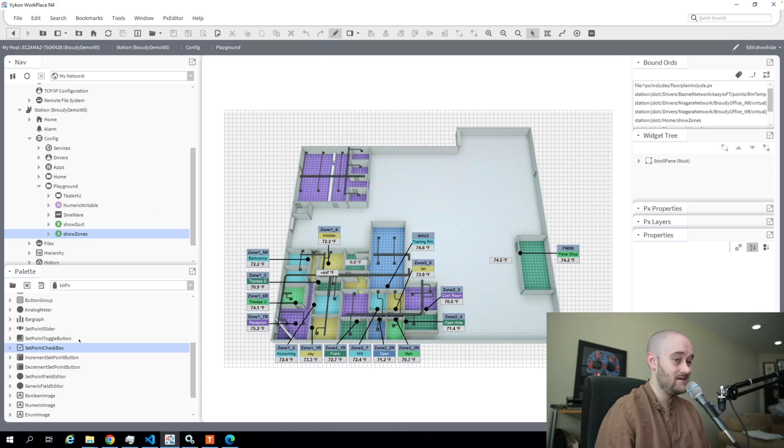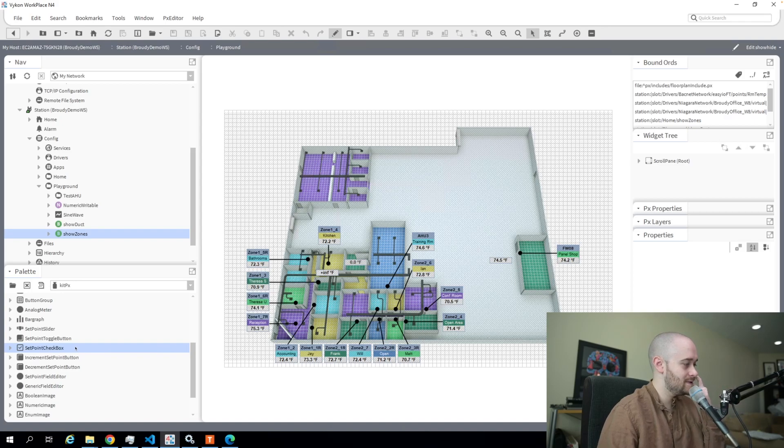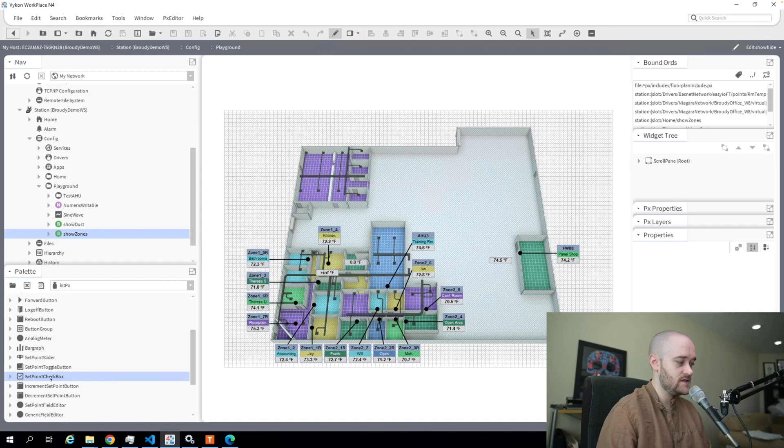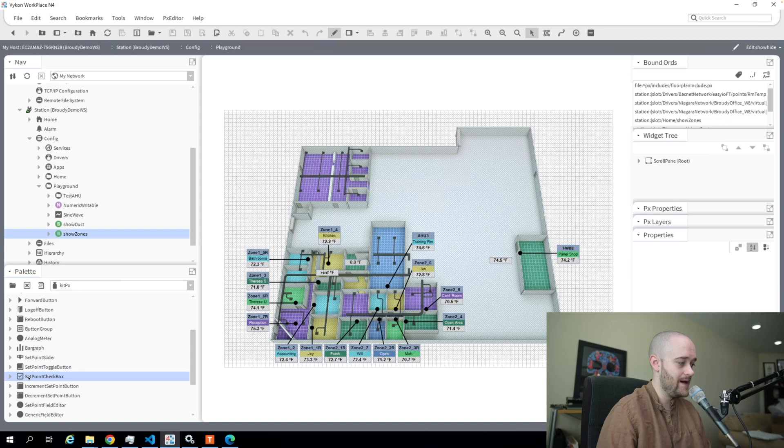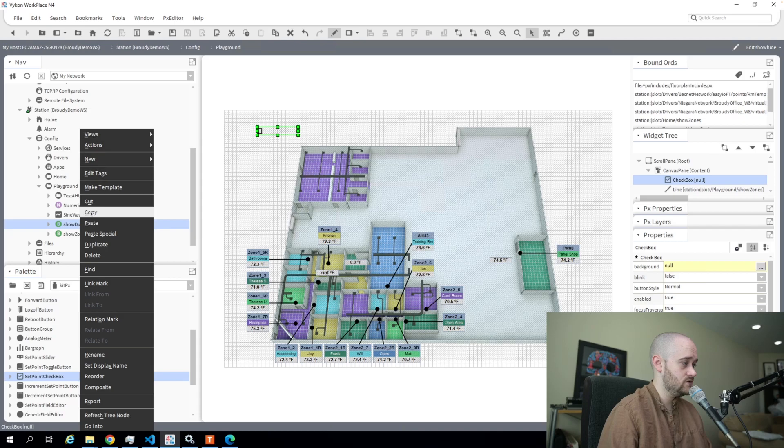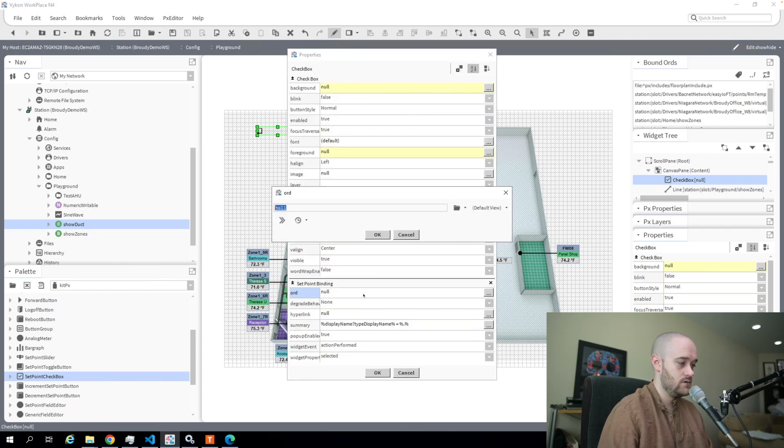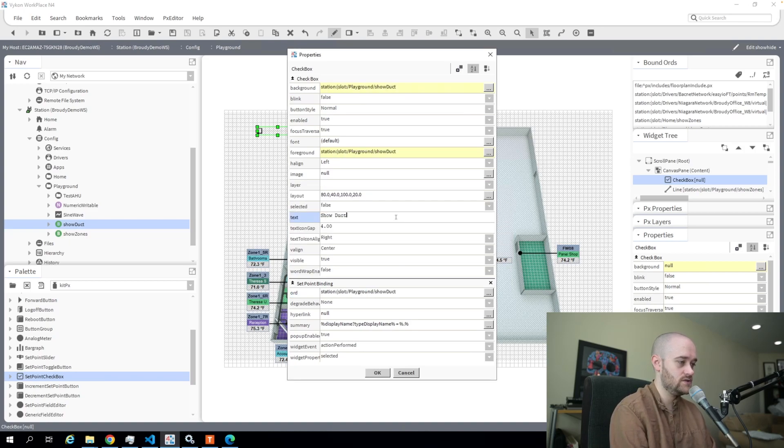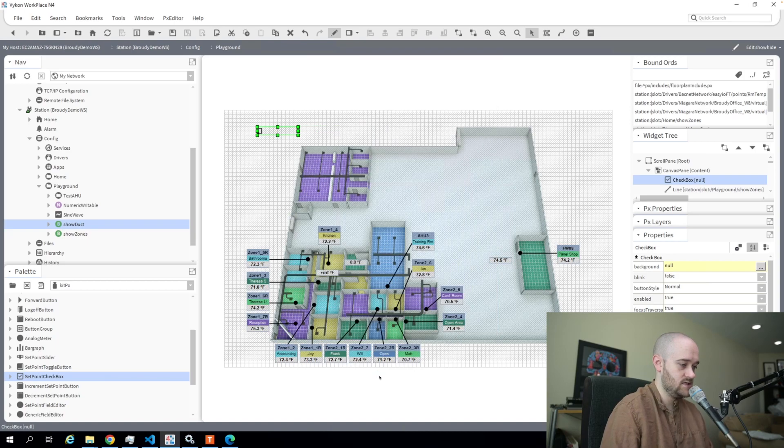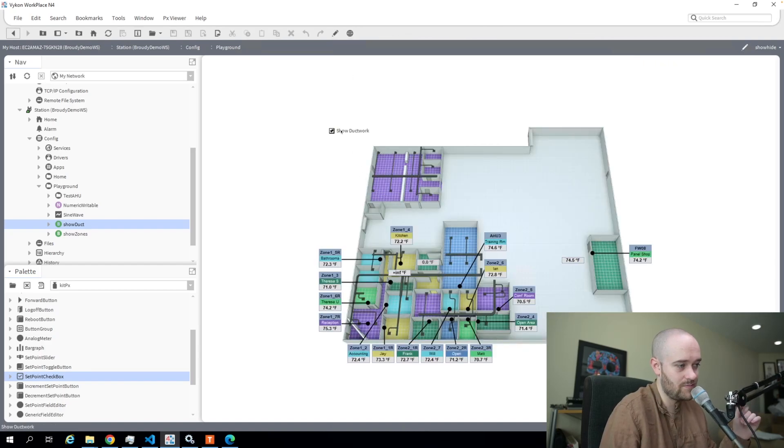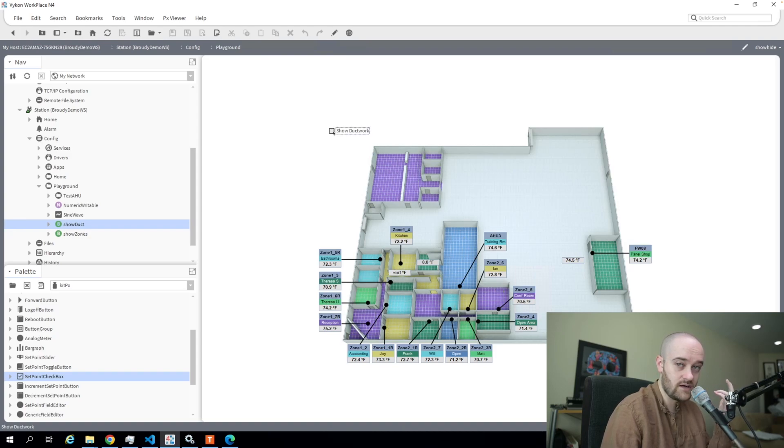The way that I like to do this—there's a bunch of different ways you could do it—but the way that I like to do it seems to be the most intuitive for a user, is to use the setpoint checkbox, which is underneath kitpx for the palette. I'm going to drag one of those out and use it to do my show duct. We will set that as the ord, and for the text I'm going to say show ductwork. That looks good. You can see now the checkbox is automatically checked; it knows that the boolean value is true. So if I uncheck it, my ductwork goes away.